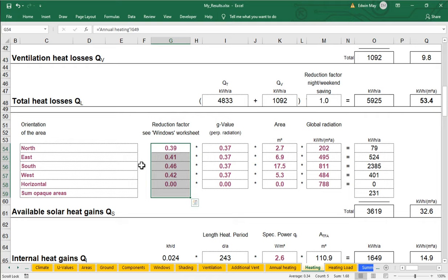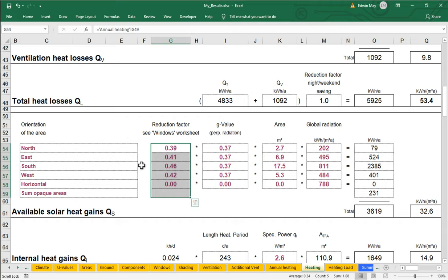So these reduction factors, and they are just that. They're just factors. It's some number between zero and one. These numbers are determined, in part, by the shading situation of each of the windows in those orientations. And if you notice the math here, everything just gets multiplied together. So as the factor gets smaller, as the factor approaches zero, what's going to happen to the total solar gain through that orientation? It'll also approach zero. So a low shading factor will result in a low solar gain. A high shading factor will result in a high solar gain.